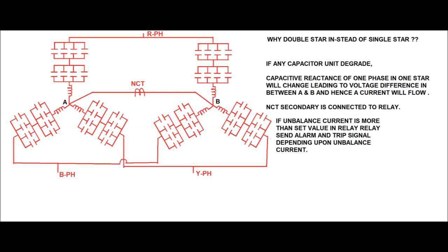The NCT secondary is connected to a relay called the neutral unbalanced current relay. If the sensed current exceeds the alarm setting, an alarm is sent to operating personnel to detect the faulty capacitor unit. If the current exceeds the trip preset value, it will trip the capacitor bank to avoid further damage. The function of the NCT is therefore to detect any unbalanced current due to a faulty capacitor unit.